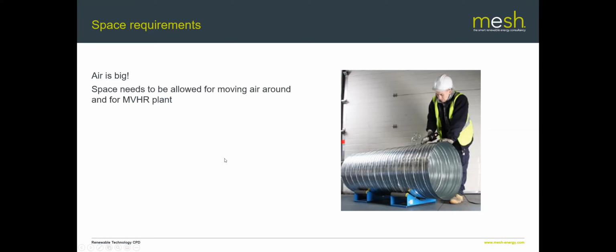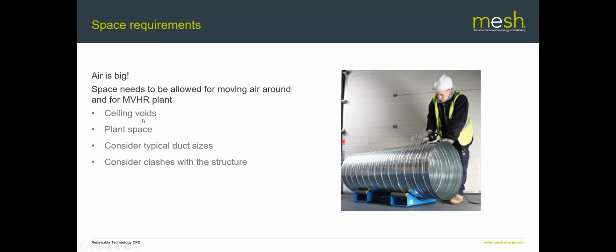So the ductwork can be quite a thing to try and package into a house, especially one where that hasn't been considered early on. So think about where that is going to go, and typically the place you put your ducts is in the ceiling void. You generally want to supply and extract at relatively high levels in the room, and that means you want to have the ceiling void. The obvious space then is to run the ductwork through the ceiling void. You also need to have the plant space. The actual MVHR unit itself has a space requirement, and the other thing to consider is that it's all very well having a nice big ceiling void, but if there's a steel that runs through the middle of it, it can make routing ductwork incredibly difficult. So a ceiling void which isn't a void all the way across is not really much use, because steels and ductwork don't really tend to be great bedfellows.